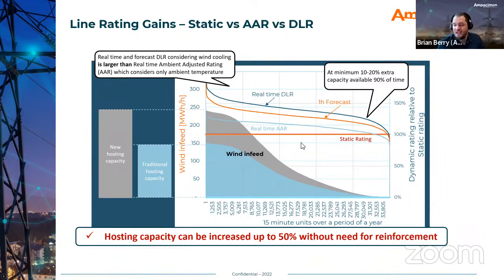50% of the time, I can have another 40%. And 90% of the time, I can have an extra 10 to 20% capacity. Okay, because what this is taking into account is the wind blowing or not blowing, etc. And exactly what Emmanuel was talking about with wind in feed, you can see on this graph here, the blue and the gray. So if you assume the static rating, remember wind power doesn't generate all the time. It only generates when the wind is blowing.